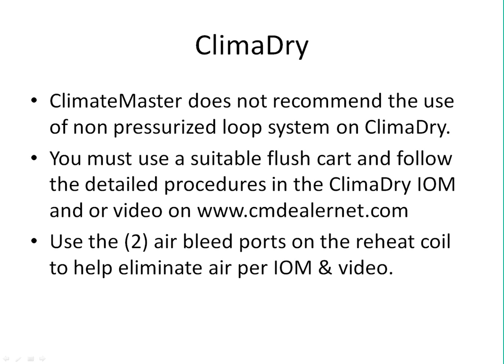One of those steps that you'll see in the video, guys, and it's also referenced in the IOM, use the 2 air bleed ports that are installed on the reheat coil. So typically they're in a high and a low corner. It's about a 1/4 or 3/8 inch diameter copper tube that's coiled up. You can actually carefully kind of unwind that, get it out to where it's more convenient to work on it. Use a screwdriver to open it up to bleed the air out while you're flushing under high pressure.